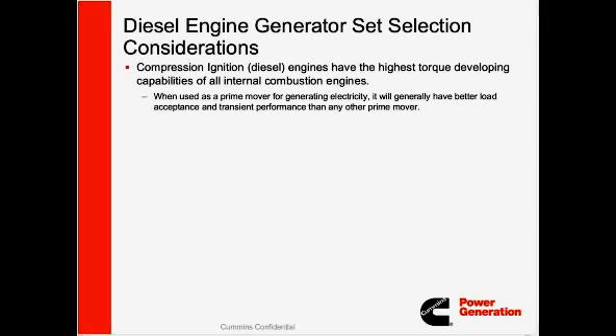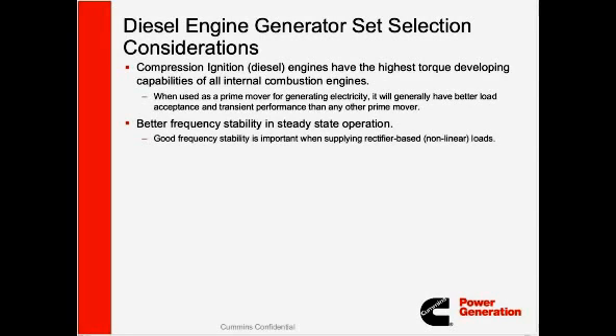Load acceptance is very important. Recovering from the load acceptance to nominal voltage and frequency within 10 seconds or 60 seconds, depending on the type of load, is very important. And with diesel engines, you can accept load much better than a natural gas generator would. Frequency stability in steady-state operation is also very important. This is especially important nowadays with the increased use of nonlinear or rectifier-based loads, such as those used in data centers, uninterruptible power supply systems, telecommunication applications, basically applications where you're converting AC to DC. The frequency needs to be stable, and diesel has better frequency stability in steady-state operation than natural gas.